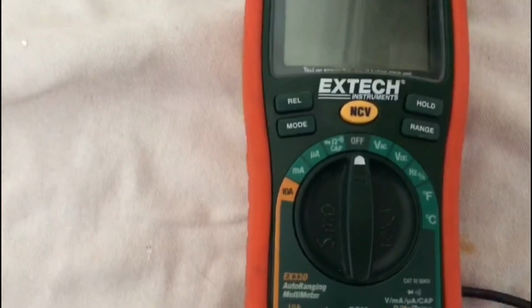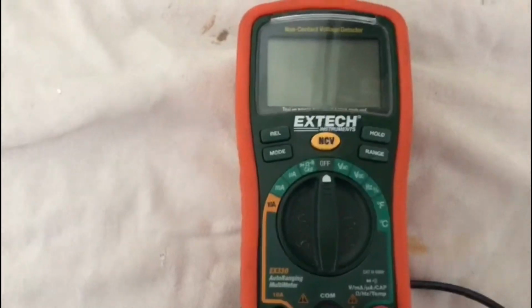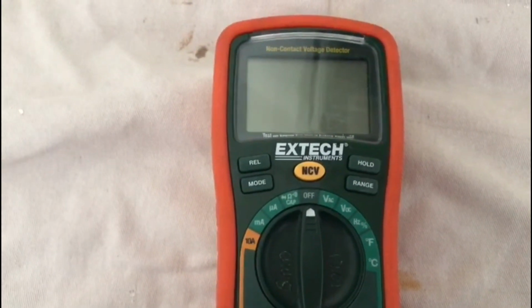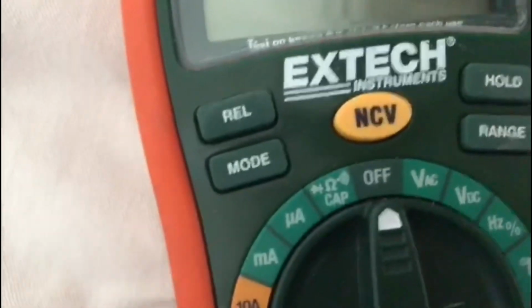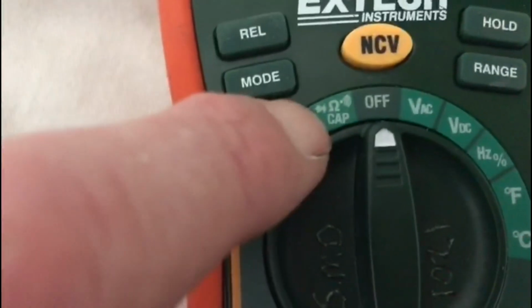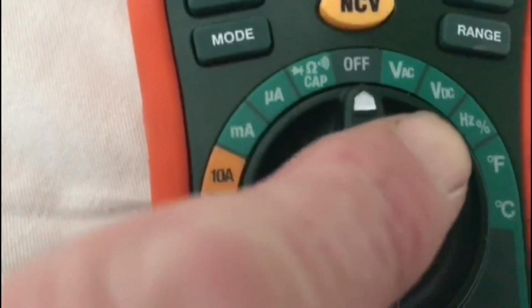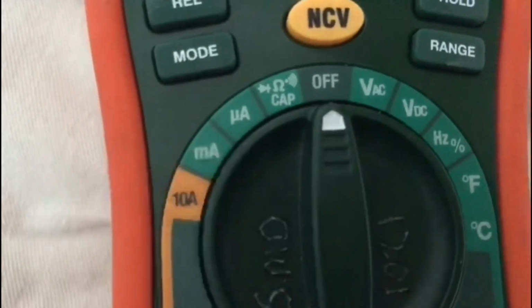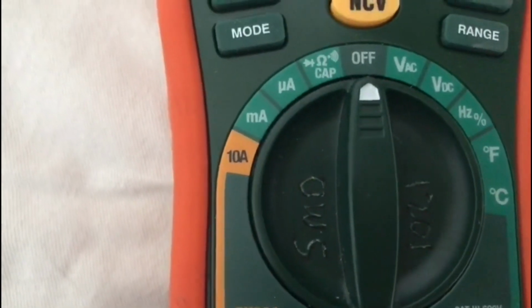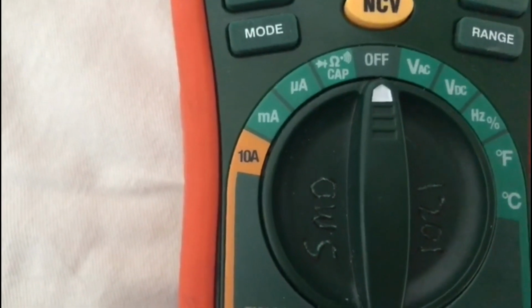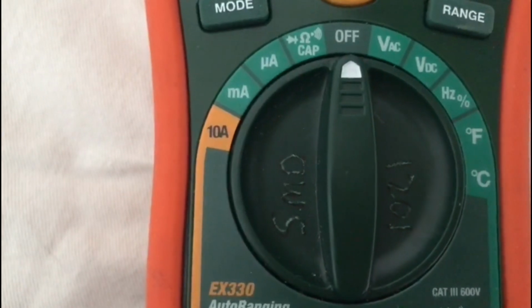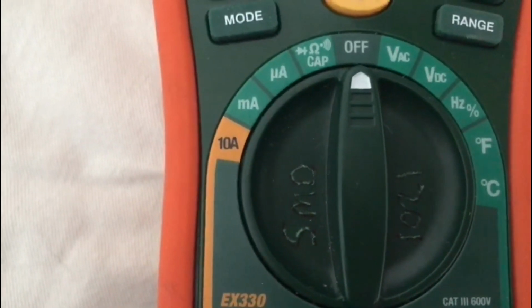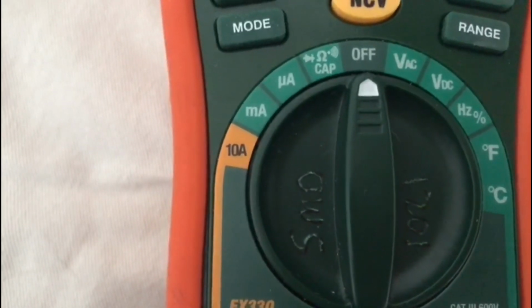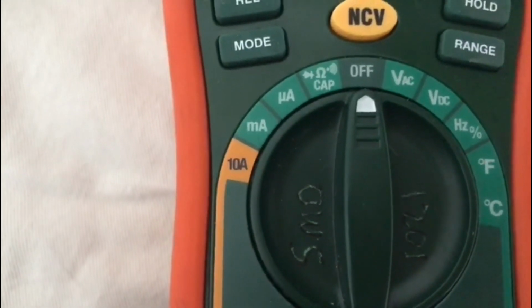Now with your multimeter, you can do it with the multimeter or a voltage tester. I'll show you the multimeter way first. On your multimeter you've got different settings. Here is the resistance, which is the ohms symbol. You've got alternating current. You've got direct current. The rest are all different things which you can measure. Some are microamps and things like that, which you can use to test things like, for example, a thermocouple. You can test the resistance of a thermocouple if you wanted to.